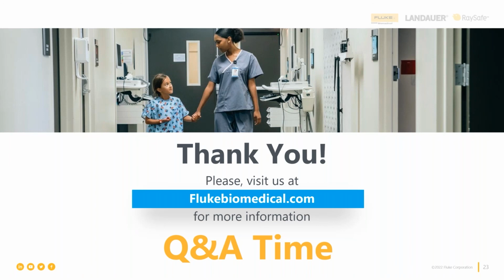There were a couple of questions around the IEC. If you could explain a little more about what that means and how it should be interpreted. The International Electrotechnical Commission, IEC, is the international body that publishes and is responsible for maintaining the minimum performance and safety standards for all medical devices. They are housed underneath this umbrella called IEC 60601. So if I just say IEC 60601, I'm talking about the umbrella. I'm not talking about the electrical safety unless I say IEC 60601-1 or IEC 62353 or IEC 61010. That's the organizational structure.